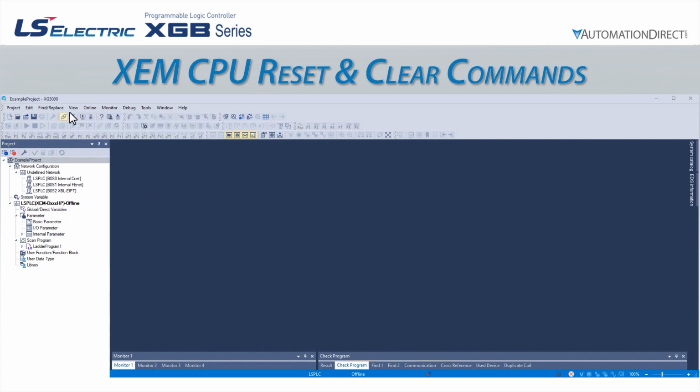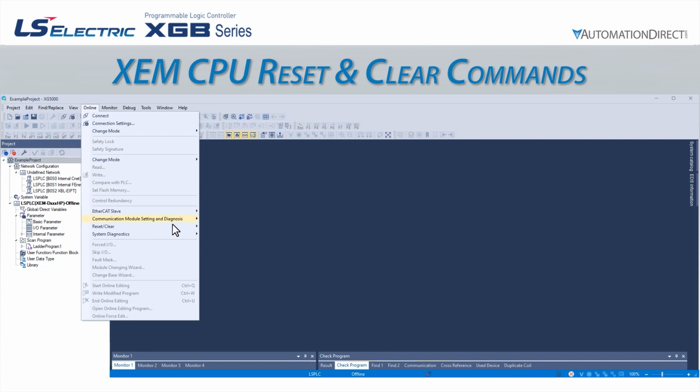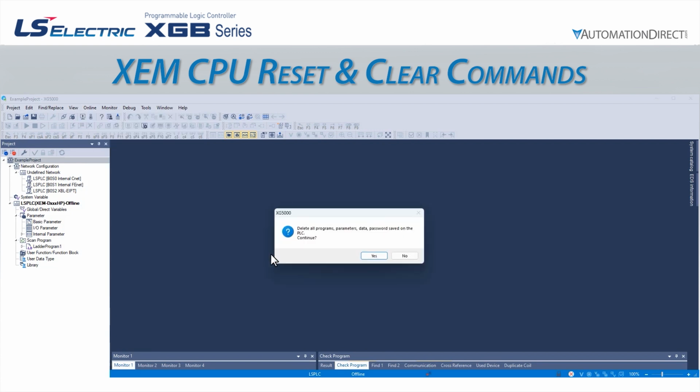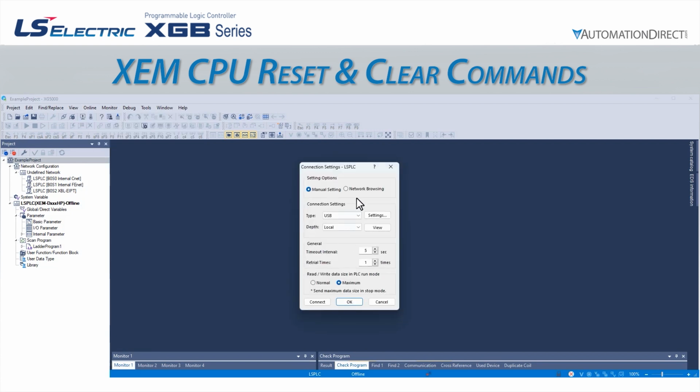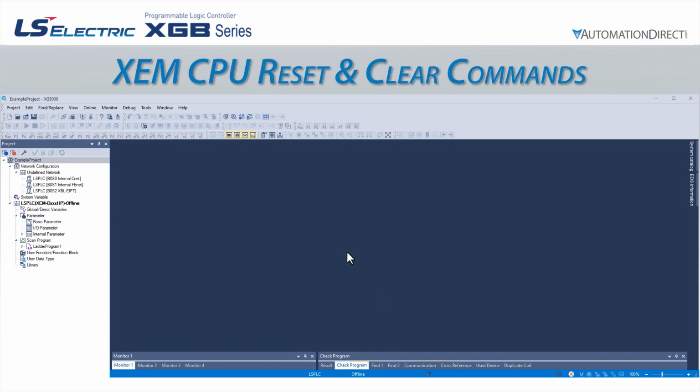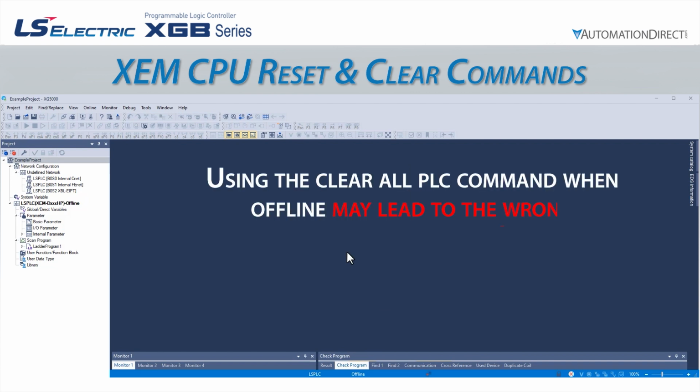We can initiate the clear all PLC command offline, as it will force us to then connect to our CPU to execute the clear all. We strongly recommend only initiating the clear all PLC command for a CPU that is already connected to the software. This will ensure we clear the correct CPU. If we were to initiate a connection as part of a clear all PLC command, it will clear whichever PLC we connect to as soon as we select connect. If we have multiple PLCs and are connecting via Ethernet, we might easily clear the wrong one.